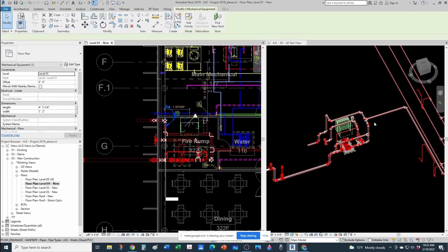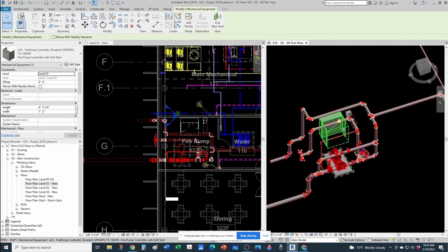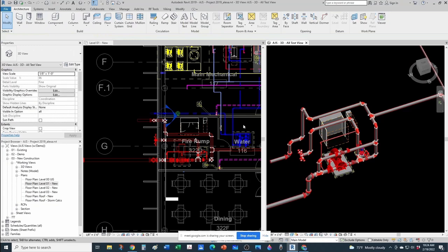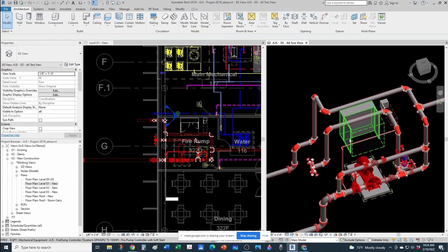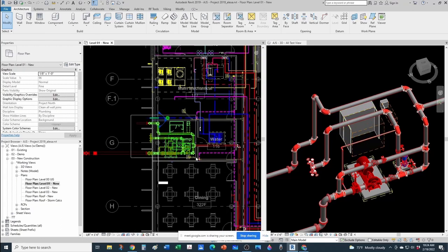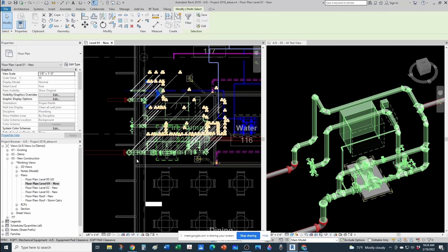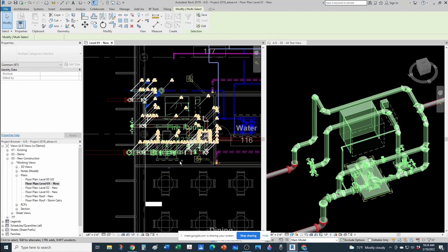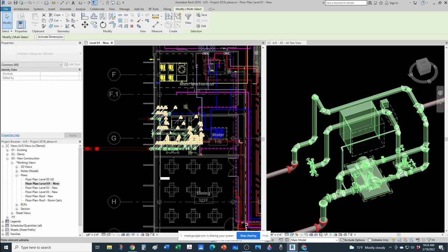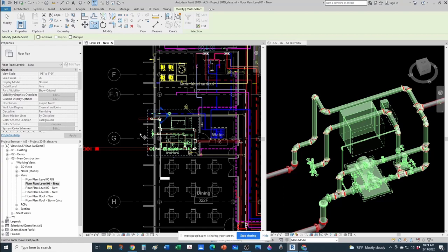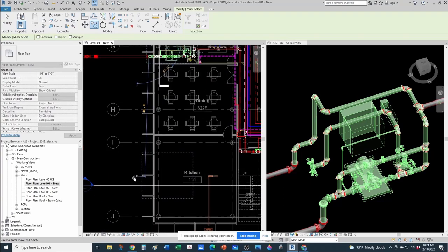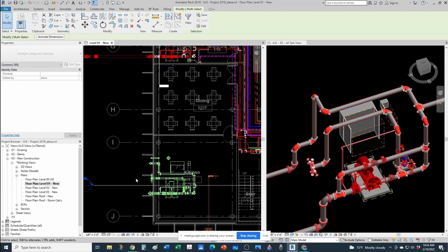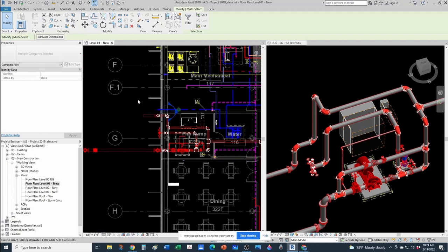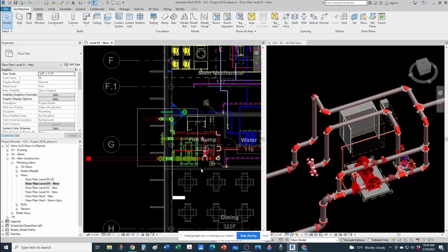And here, of course, you have your main fire pump controller and your jockey pump controller. And you want to leave at least 3 feet from the face of that controller. That's a National Electrical Code requirement. Let's just grab this. Let's see if this works like that. Let's grab this and take it out of the way, and then we'll just replicate the same thing. I'm going to actually copy it from here to here, and then simply delete all this, and then we'll try to recreate that.